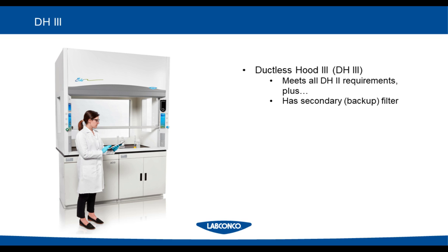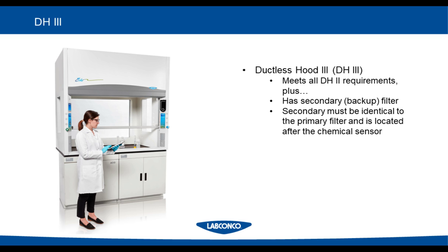Finally, we will talk about the DH3, or the ductless hood 3. This hood meets all of the DH2 requirements, plus, and this is a big one, it has a secondary backup filter. In particular, the secondary filter is identical to the primary filter. Where the DH2 lacks in safety is that if you are using the hood and the chemical breakthrough sensor goes off, you don't have a whole lot of time to clear out everything that's in the hood. Once that chemical sensor is going off, there's a potential that that chemical or vapor is escaping into the lab space.